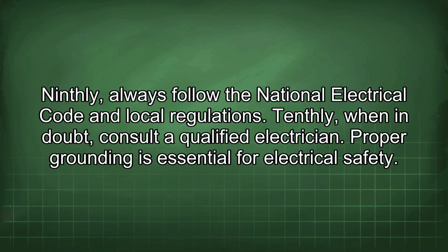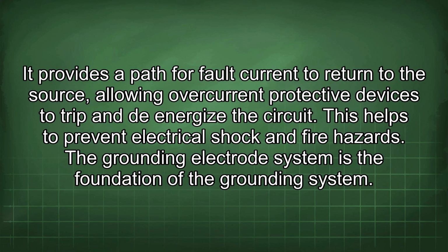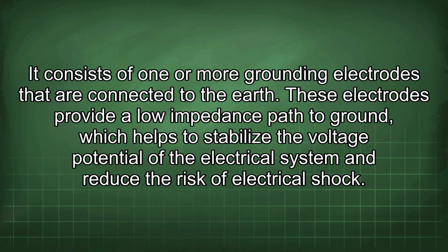Proper grounding is essential for electrical safety. It provides a path for fault current to return to the source, allowing overcurrent protective devices to trip and de-energize the circuit. This helps to prevent electrical shock and fire hazards. The grounding electrode system is the foundation of the grounding system. It consists of one or more grounding electrodes that are connected to the earth. These electrodes provide a low impedance path to ground, which helps to stabilize the voltage potential of the electrical system and reduce the risk of electrical shock.